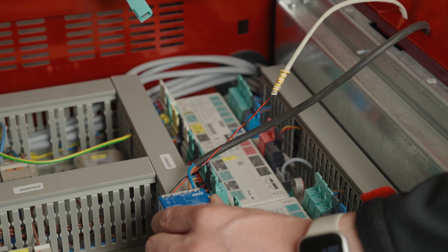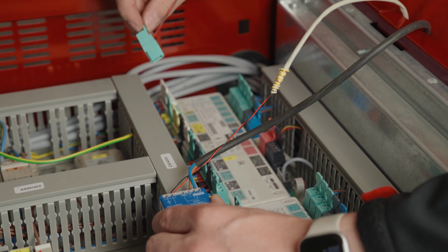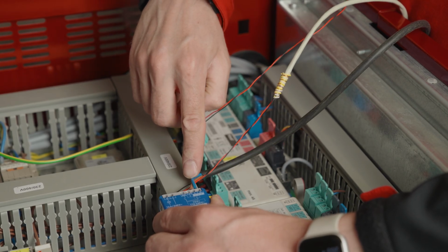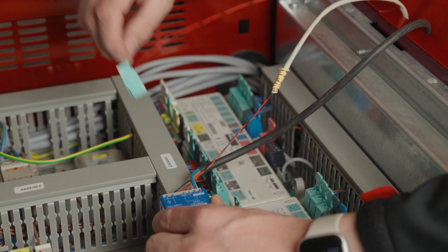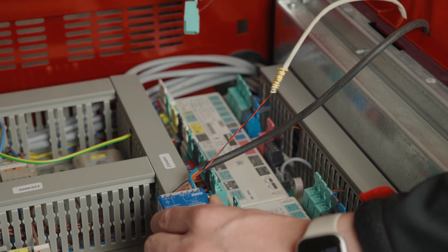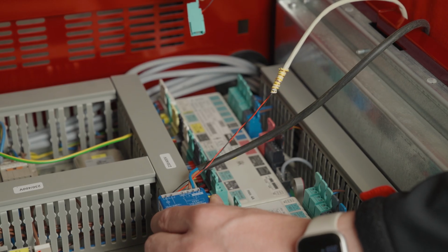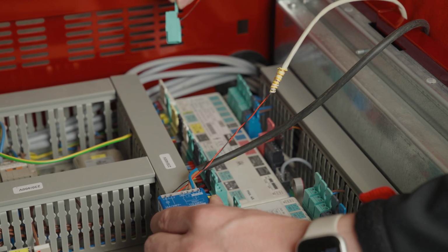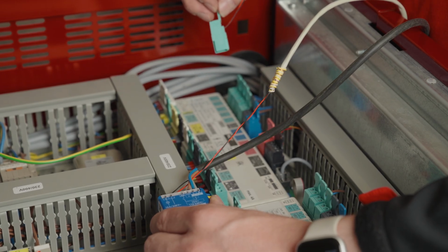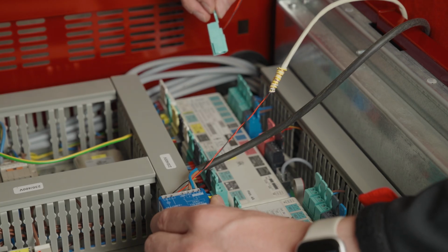For the terminal connection of the Shelly Plus 1 Gen 4, it is necessary to power it via a 230 volt operating voltage supply and to connect it on the output side to the potential-free switching contact and a potential-free input or digital input of the Hoval TopTronic E. In this case, we can do that on the WE set module, which is permanently installed in every Hoval heat pump as delivered. We can plug it in there.